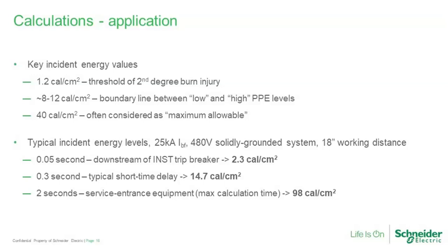If you look at those PPE levels, you get up somewhere around 8 to 12 calories. That really is what I'll characterize as a boundary line between low and high rated PPE. What I mean by that is, at 8 to 12, you can probably get by with a coverall that's relatively comfortable, or even treated shirts and pants that give you protection to that level. You get up to the higher levels, the 30 calories, 40 calories, things in that range, you're talking about wearing dedicated flash suits with hoods, rather than just face shields, quite a bit more intrusive in terms of the protection that's required.